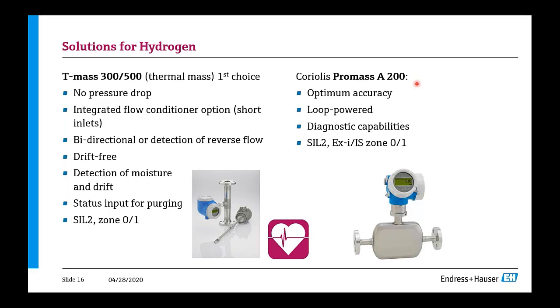Coriolis: here the Promass A200 is a 2-wire mass flow meter for small line sizes, as you usually use here in hydrogen. That's the best accuracy you can get. It's loop powered, and it's got nice diagnostic capabilities as well. It comes with SIL2 and even Zone 0 approval for the device. Both have got that: Zone 0 inside the tube and Zone 1 for the electronics.